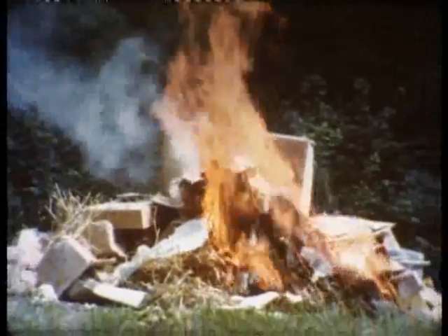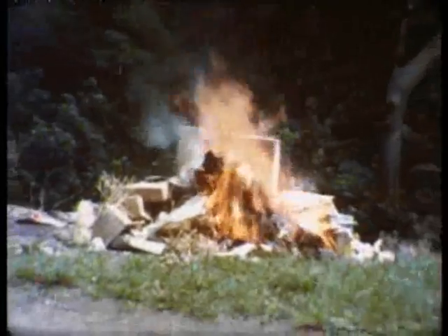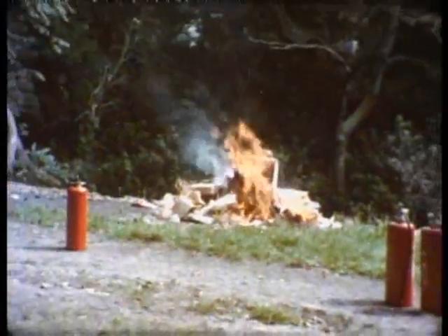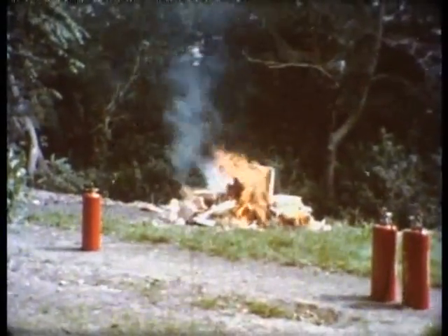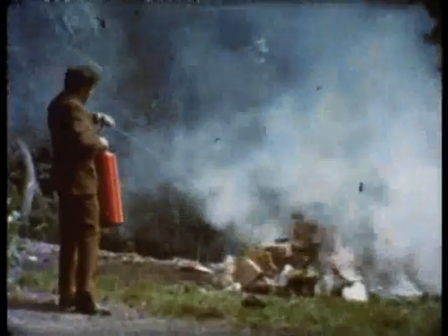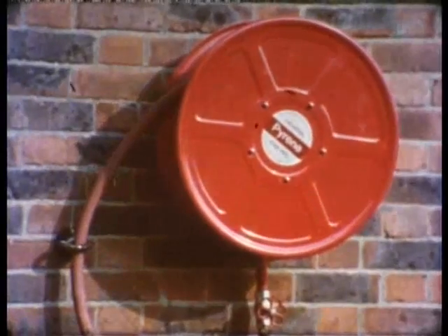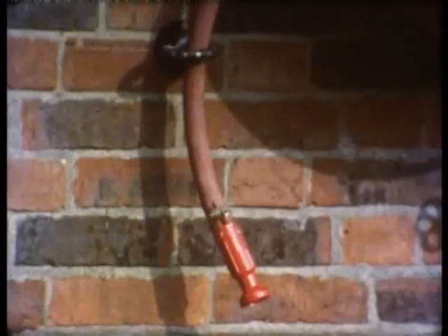This is a typical Class A fire. It comprises mostly wood shavings and cardboard, but it could have involved any number of free burning materials, such as wood, paper, cloth, or soft furnishings. Because it acts as a cooling agent, lowering the temperature of the fire to a point where it will no longer burn, Class A fires can be fought with water using either an extinguisher or the more powerful water jet provided by fixed-type water hose reels.